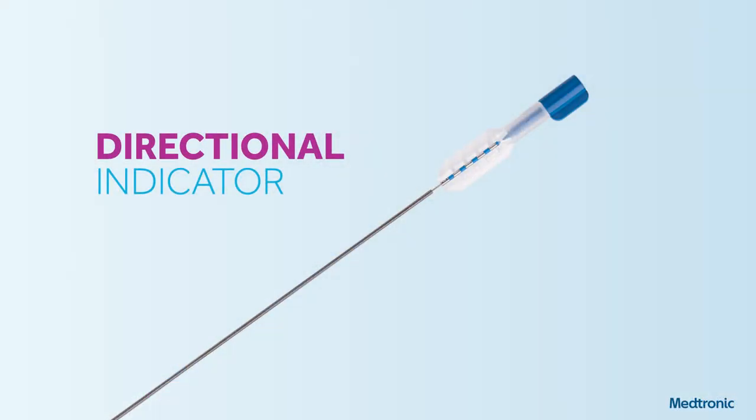Dr. Klausche, what have you noticed about the feel of the lead? The lead itself hasn't changed a lot in its core, except it already has the curved component preloaded, which is excellent since I was using that 99% of the time anyway. At the very top of the lead, there is a directional guide that is a little different. It helps visualize or locate the direction the curve is going, so implanters can use it to assist in placement — angling it 10 or 30 degrees — without having to rely on memory alone.